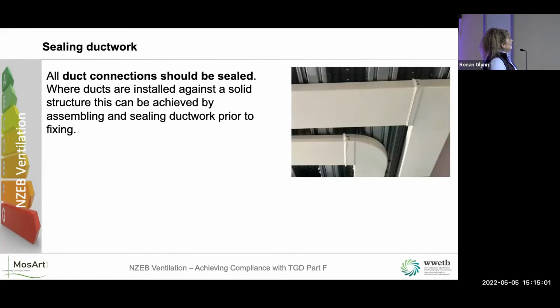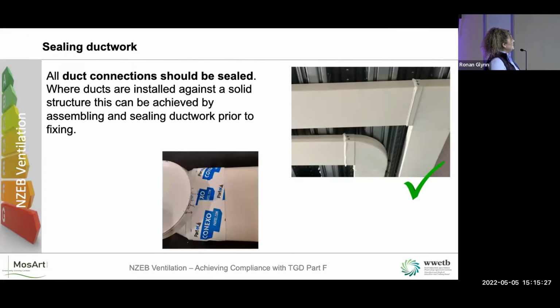So all duct connections should be sealed. Where the ducts are installed against a solid structure, this can be achieved by assembling and sealing the ductwork prior to fixing, which is grand. But if you have a big, long stretch of ductwork, it's pretty impossible to do that. So 9 times out of 10 on site, what you'll see is a bit of airtight caulk, the two pieces of ducting are put together and you get a little self-tapper screw to hold it together. Otherwise, you can have a piece of airtight tape on your ducting.